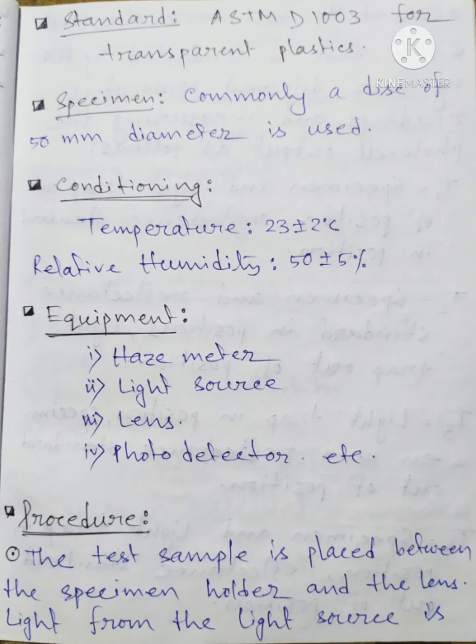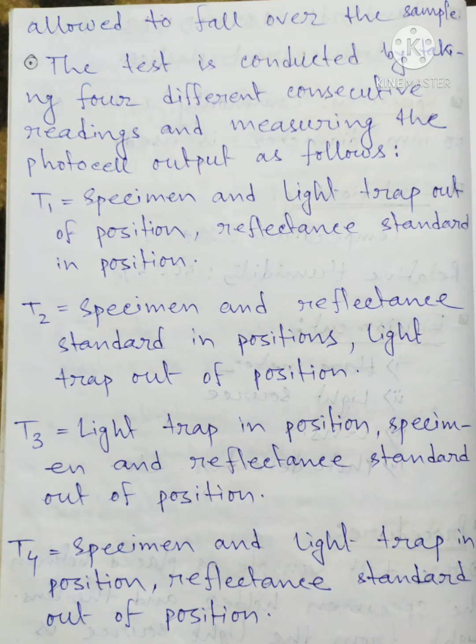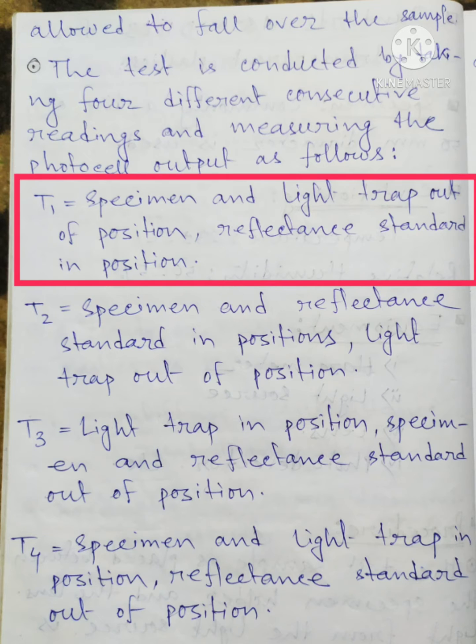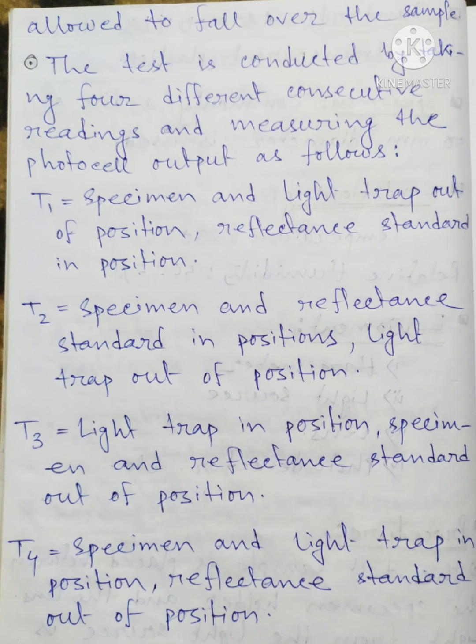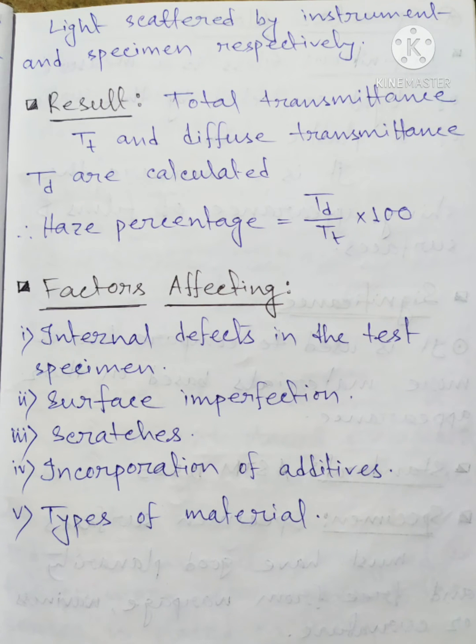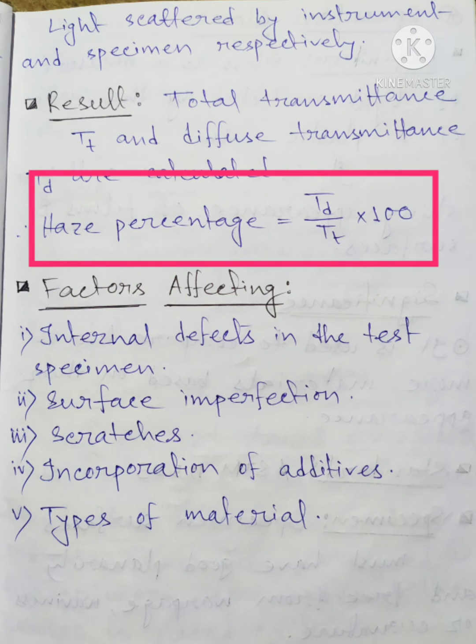For the procedure, the test sample is placed between the specimen holder and the lens. Light from the light source is allowed to fall over the sample. The test is conducted by taking four different consecutive readings and measuring the photocell output. T1: specimen and light trap out of position, reflectance standard in position. T2: specimen and reflectance standard in position, light trap out of position.